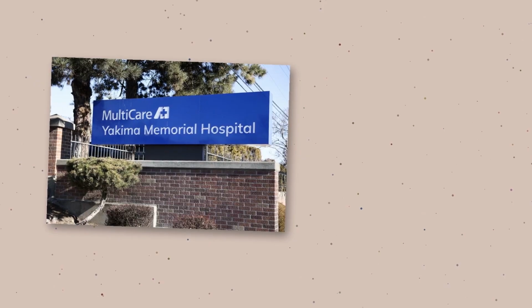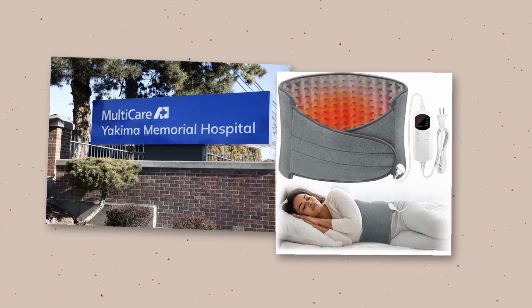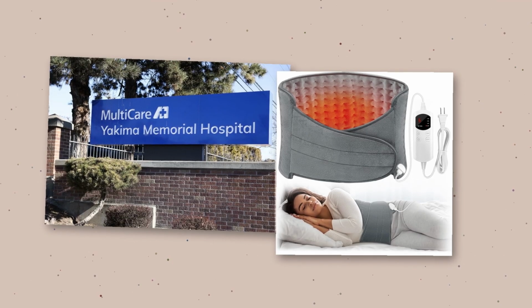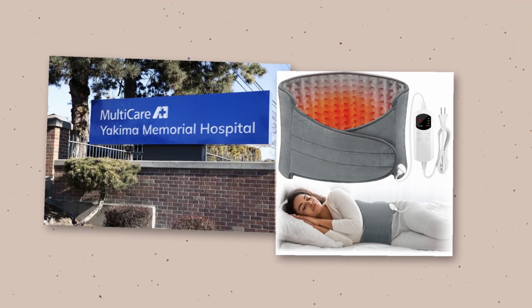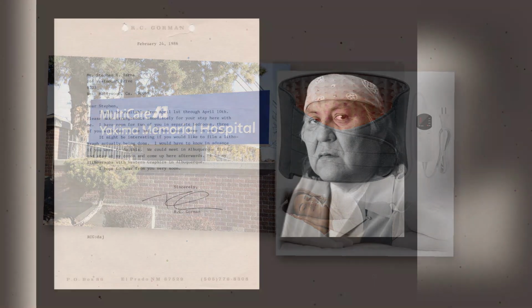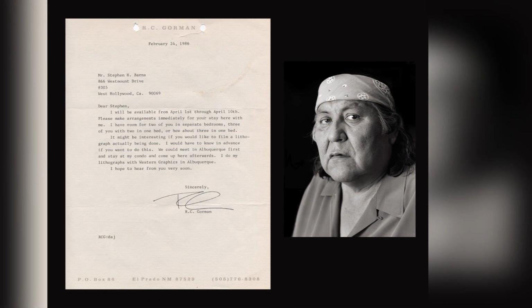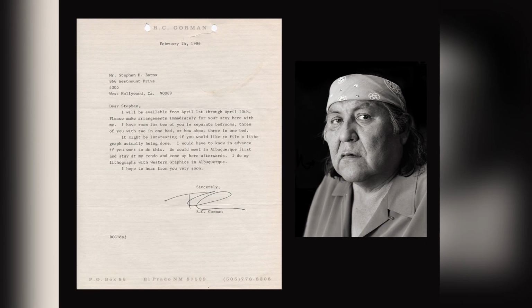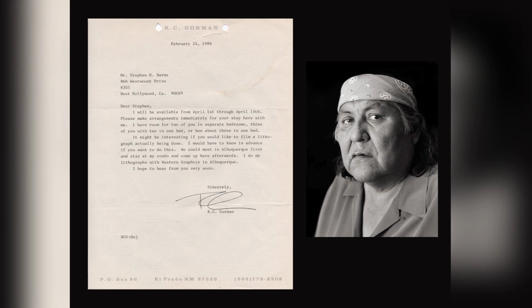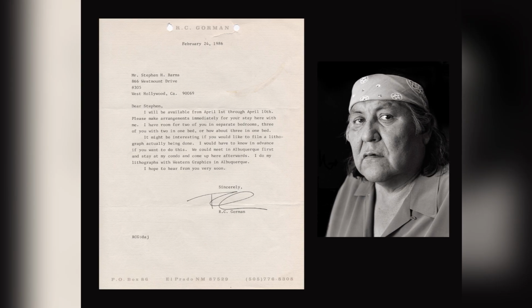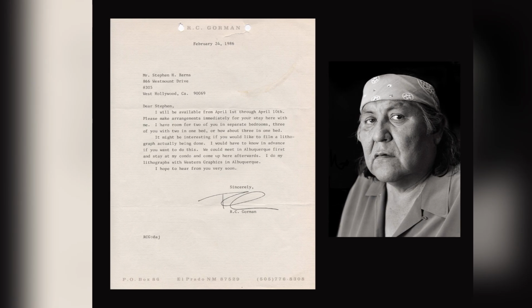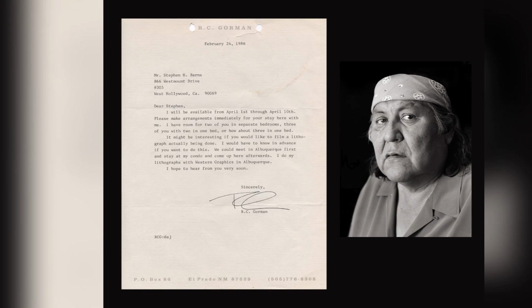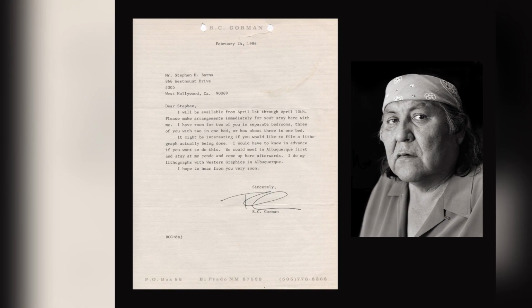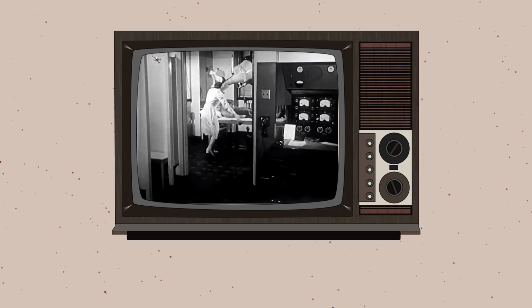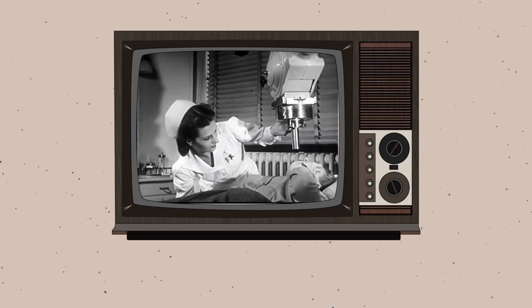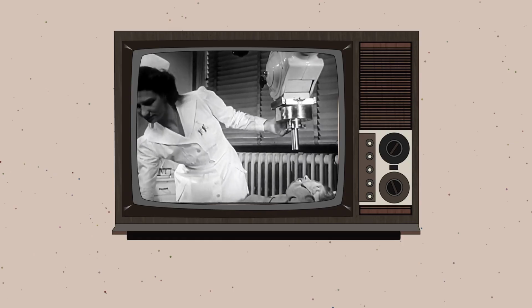December 1985, at Yakima Valley Memorial Hospital in Washington, a woman developed reddening on her hip in a parallel striped pattern, and staff x-rayed her electric heating pad to see whether its wires matched the marks. They did not. On February 24, 1986, AECL's technical support supervisor wrote to the hospital that the damage could not have been produced by any malfunction of the Therac-25 or by any operator error, and set out 2 pages of technical reasons why an overdose was impossible. Recorded cause: unknown.